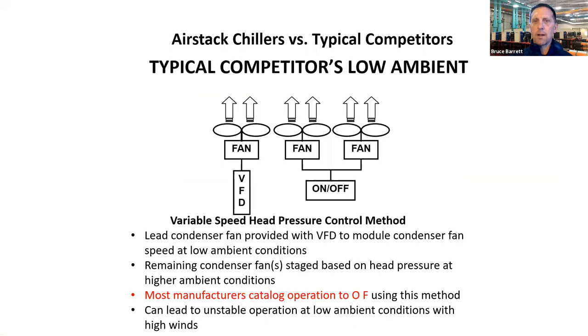All right, what do modular chillers do different? What we do is quite a bit different than package chillers. When they have a scroll or small screw machine, they often have what they call fan troll. They've got standard fans that are on and off, but they have one or two of their fans controlled by a VFD. They've got to build enough head pressure, control the fans well enough to build that head to be able to start those compressors.